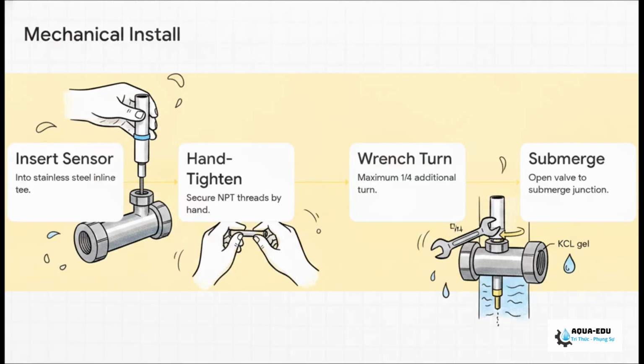Let's break down the mechanical steps. When you're mounting the sensor into that stainless steel inline insertion tee, hand tighten the NPT threads first. Then, and this is super important, only use your small wrench for a maximum of 1/4 additional turn. Any more than that and you risk cracking the body. Once it's locked in securely, make sure you actually open the isolation valve. The water has to submerge the sensor so it can activate the KCl gel inside the reference junction.